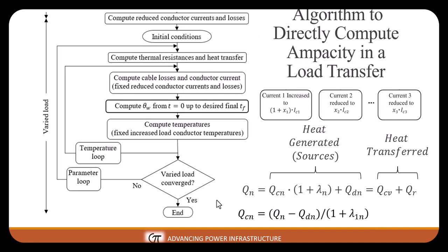Here is the algorithm to directly compute ampacity in the load transfer. Let's say we have cables 1, 2, and 3, and we want to reduce load in cable 2 by fraction x2 and reduce load in cable 3 by fraction x3.